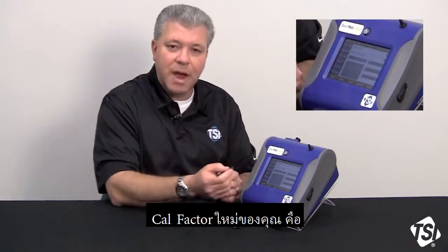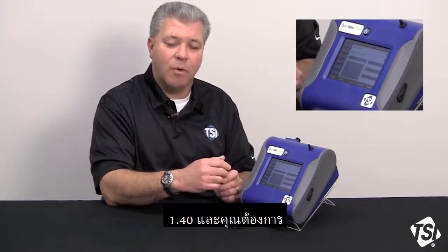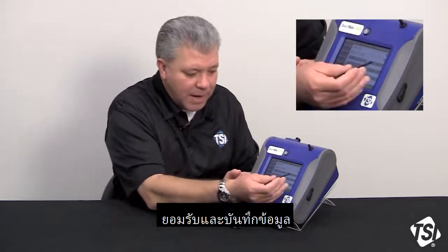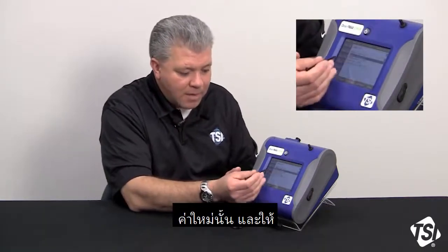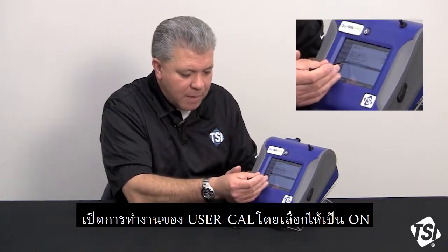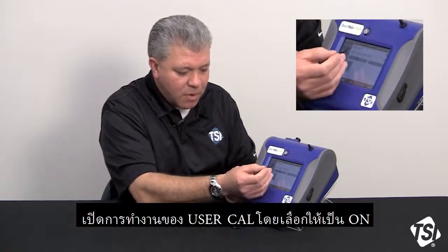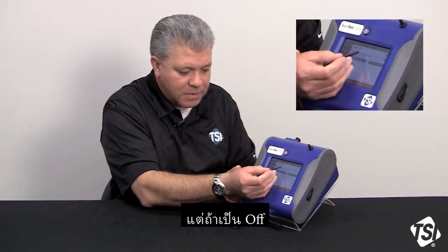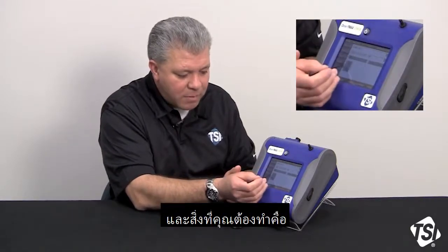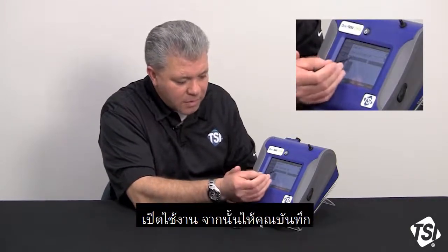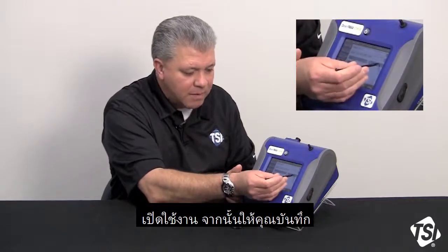Let's say that your new cal factor came back at 1.40. You would definitely want to go and accept that, okay, save that new number, and then you want to go and enable that user cal. So on this bottom row here, it'll say user cal off, and what you want to do is toggle it so that it is on, and then you save that.